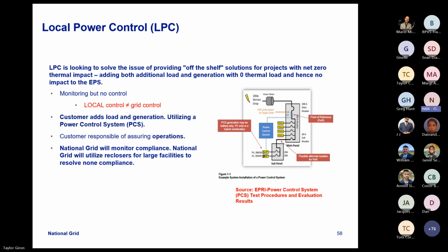There is no grid feedback to dictate what the site should ramp up or down to. A project with this type of controller would be studied to a particular load profile at the facility. These are more commonly seen as best applicable to behind-the-meter systems, usually of a smaller size. The site would get evaluated to a certain load profile, and the controller would help the customer actively manage staying within those local load profile boundaries.